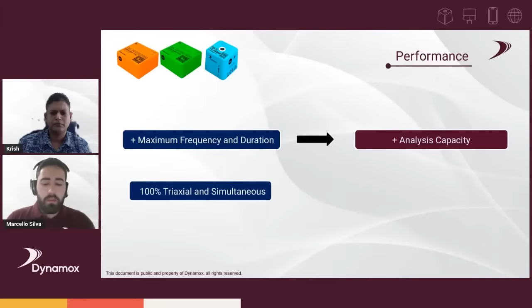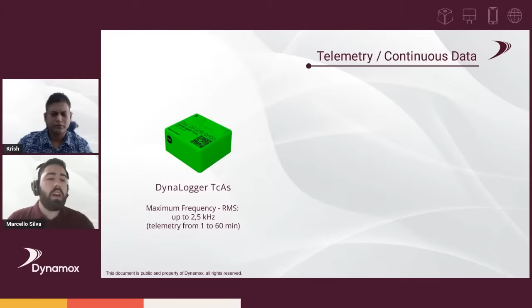In terms of telemetry, or continuous data, telemetry is what we call measurements that are taken continuously: the sensor wakes up, collects a sample, stores it in its memory, waits for the next sample interval, and then does it again, repeating. For the TcAs, this telemetry goes from 1 to 60 minutes, so you can configure that. Maximum frequency in RMS is up to 2.5 kilohertz, a big improvement from the previous sensor. The TcA Plus would go to 124 hertz, and this one 2.5 kilohertz. For the DynaLogger TcAg, it's the same thing: up to 2.5 kilohertz and telemetry from 1 to 60 minutes.